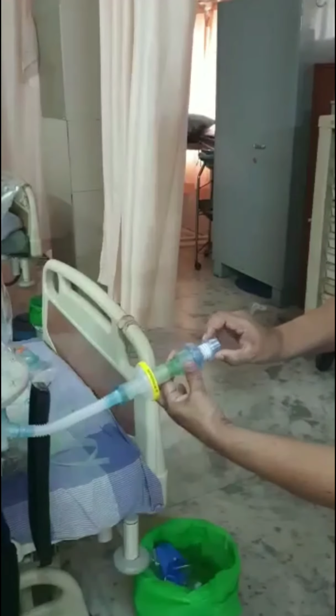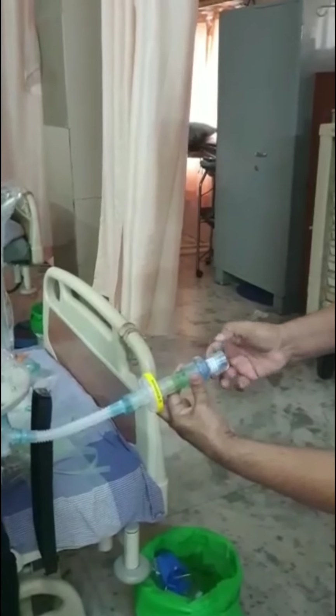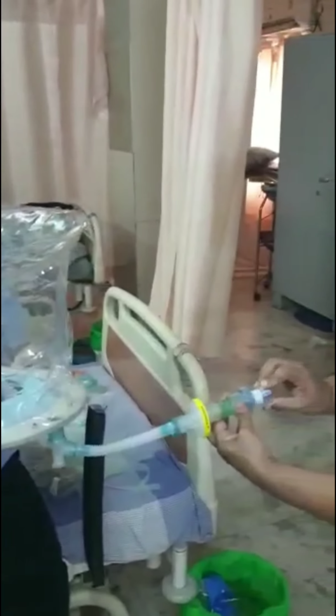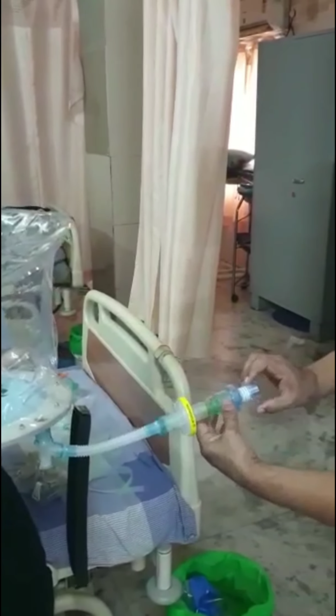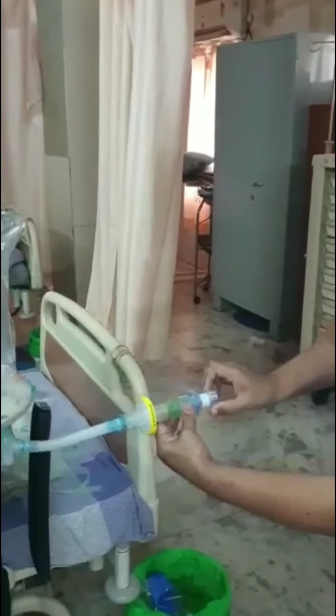cm. This PEEP has to be adjusted to the comfort of the patient. If the patient feels there is too much of pressure in the hood, we have to release it. If patient feels there isn't enough pressure, we can tighten and give more PEEP to the patient. So that takes care of the expired gas.